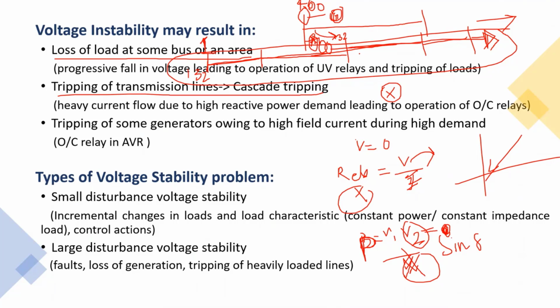When you are not able to provide that much reactive power support in between, then there will be a voltage collapse at some point in between, and there the V will be zero. And there its distance protection will start operating. So this is the situation that you face during voltage instability. And again, some generator, owing to high field current, because voltage collapse means you have to inject very high reactive power to maintain the voltages. That may result in very high field current, and that can result in the overcurrent relay in the AVR operating to protect your field circuit. So that is also one of the problems that we face with voltage instability.